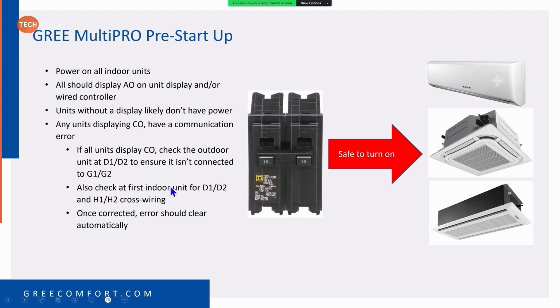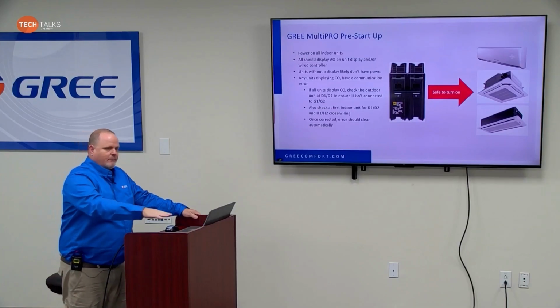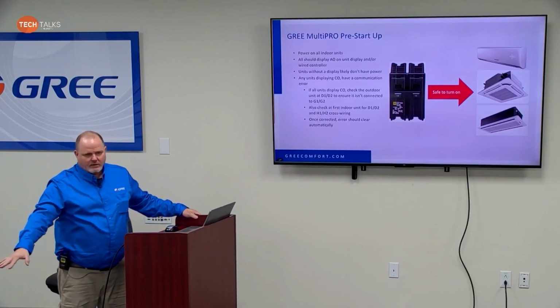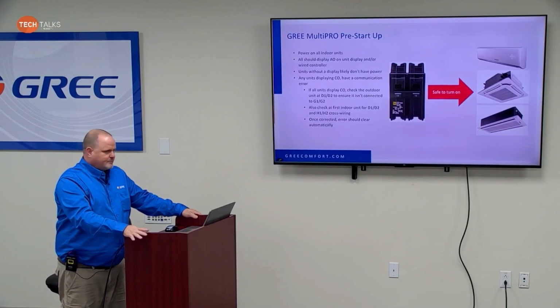You need to go through the indoor units, walk through, make sure all of them say AO before you start that unit up. Because if you start that unit up and you have one of the units that's in CO, it can't address properly. It's never even going to pick that unit up. So instead of you having 4 indoor units, you're only going to have 3. That's a problem. Okay, we are going to play that short video with James on the startup.